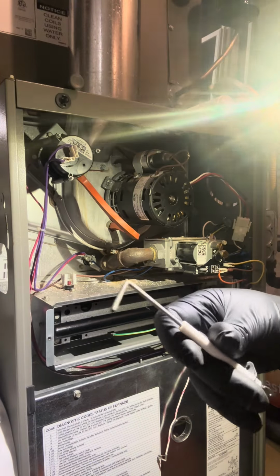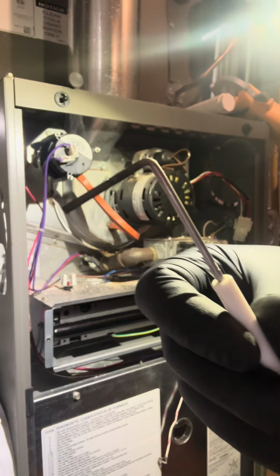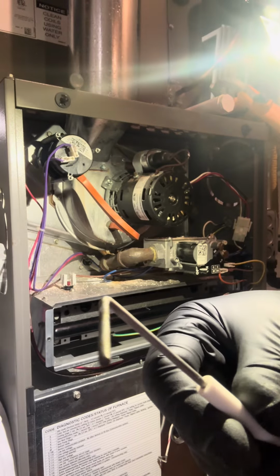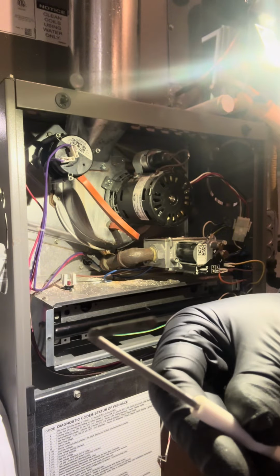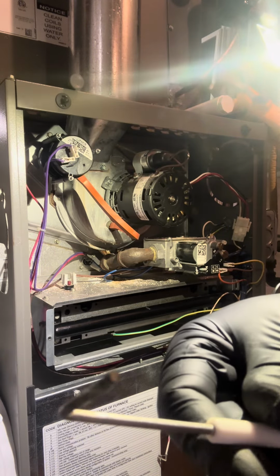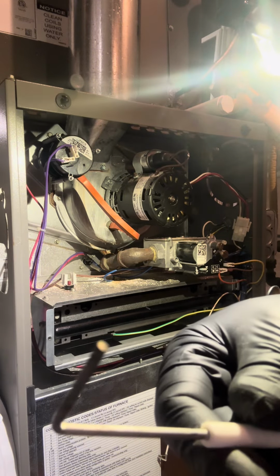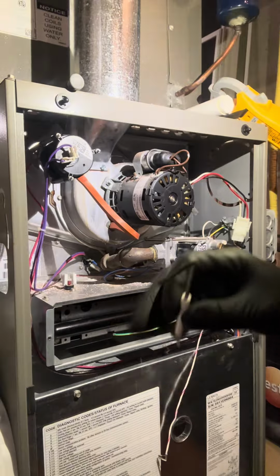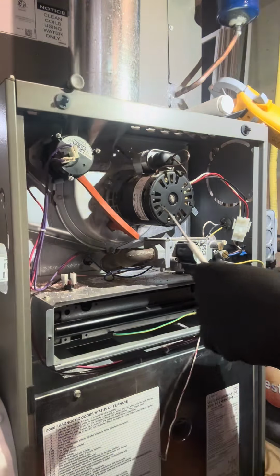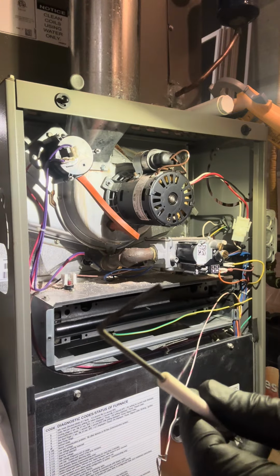So you can see, I don't know how well you can see that in the camera, but it sits in the flame and it gets nice and dirty. And if this eventually gets dirty enough, you will not be able to sense flame and it will shut your system off. So we're going to grab a steel brush and we're going to clean this off.